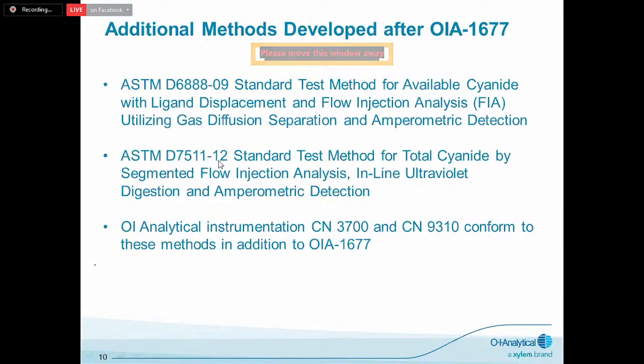ASTM 7511-12 is the standard test method for total cyanide by segmented flow injection analysis, inline ultraviolet digestion, and amperometric detection. I think I have a schematic of this one coming up a little bit later. In this one, in addition to the reagents that are used, there is also an inline UV digester for digestion of the very hard to oxidize or digest samples. And then OI Analytical instrumentation, the CN3700, CN9310, conforms to all of these methods in addition to OIA 1677.